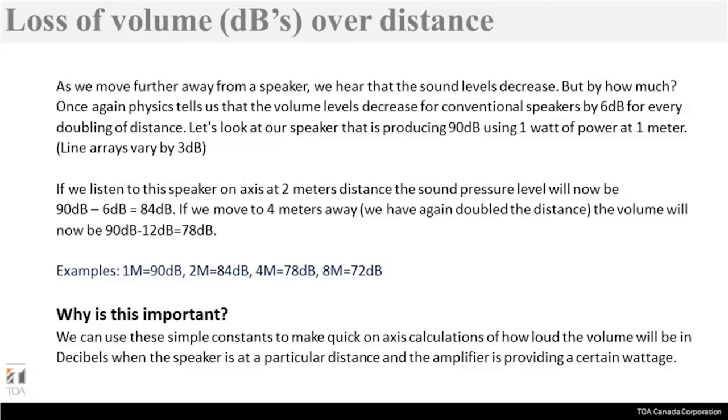So you can just imagine, 4 meters away, and just see the amount of drop. Technically, it is, I think, 13.2 feet away from the speaker, and the dB level has dropped from 90 to 78. So you have to be very careful, because when you are working on a design, you got to make sure that the sensitivity of the speaker is up to the level that you're going to need. At the same time, you have to take into consideration how far the person who's going to be listening to the intelligible announcement is going to be, and based on that, you gotta set the tapping on the speaker.